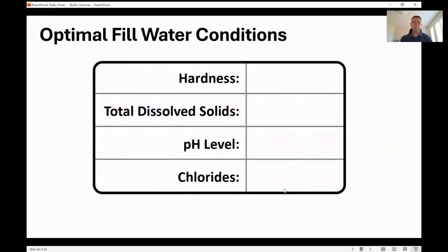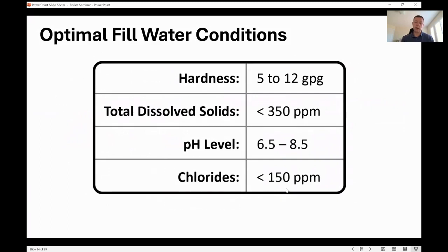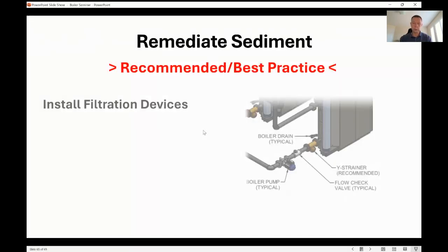Most gas boiler manufacturers will require levels like this: hardness between 5 and 12 grains, total dissolved solids generally below 350 ppm, pH between 6.5 and 8.5, and chlorides, of course, you want below 150. Now, electric boilers are different. Most electric boiler manufacturers require significantly less dissolved solids and less hardness in the water. Generally, there are electrodes in a little tank of water, so they can be prone to lime up. So always check your boiler's water quality requirements.